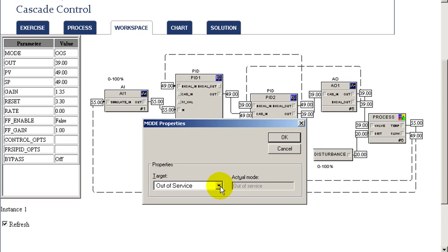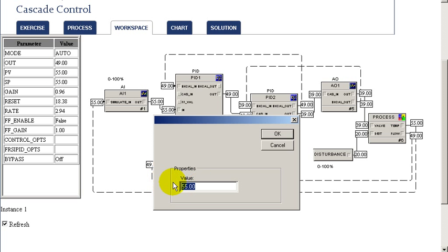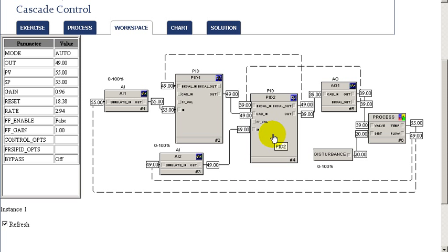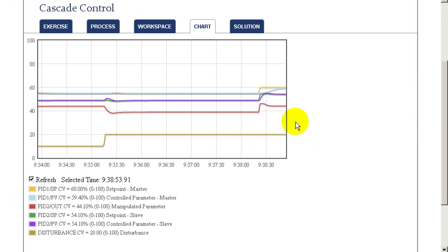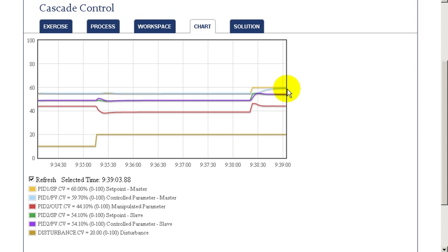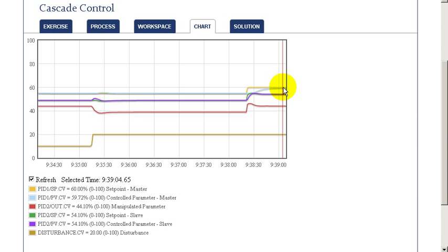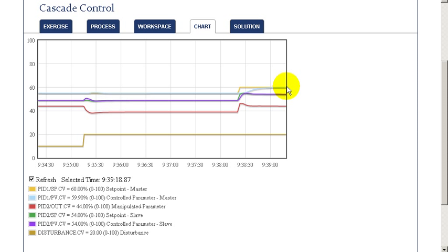Having done this, we can now put the control loops back into service and examine the behavior for a setpoint change in our master loop. We'll change the setpoint by a step. As before, when we do a setpoint change, it impacts the setpoint of our slave loop, which then adjusts the output, and through that we're able to achieve the setpoint of our master loop. Looking at the chart, we can compare this to the previous response and see a very good dynamic response using dynamic reset. This is especially helpful where the process gain of your secondary changes over its operating range, as dynamic reset can really improve the overall dynamic performance.